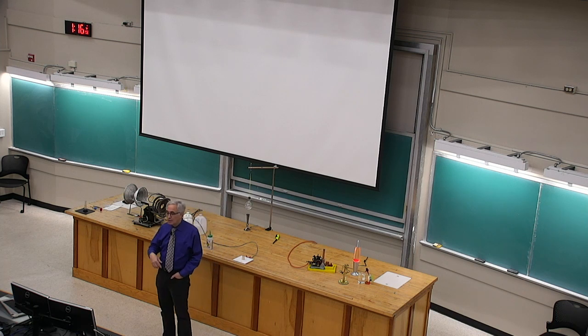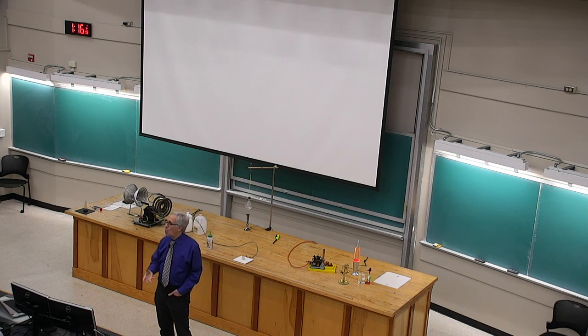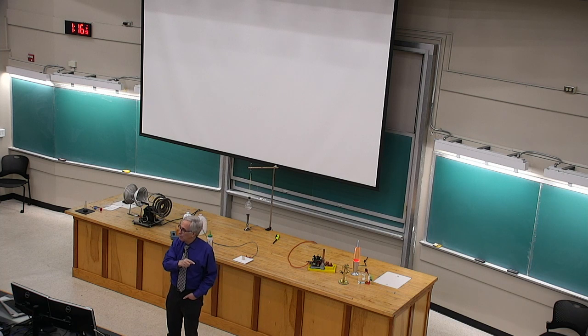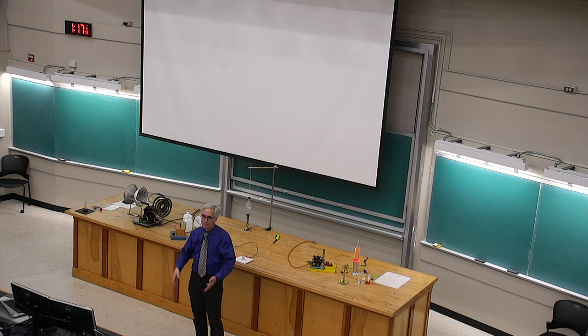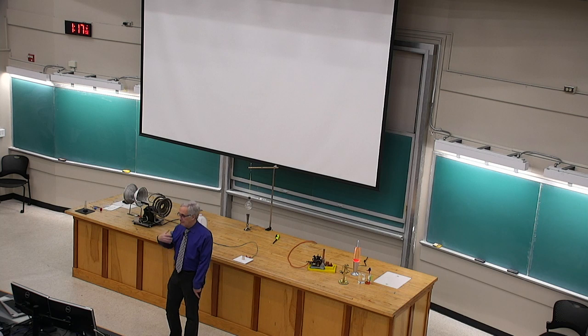And what the heat pump does is it goes outside and gathers 4,000 watts of thermal power from the surrounding air and carries it inside at the expense of 1,000 watts of electric power. And what is then dumped off inside is both. It's the 4,000 watts you gathered of thermal power plus the 1,000 watts that you had to create out of electric power. So 5,000 watts shows up in the house, but all you bought from the electric company is a fifth of that. So that's what heat pumps do for you.